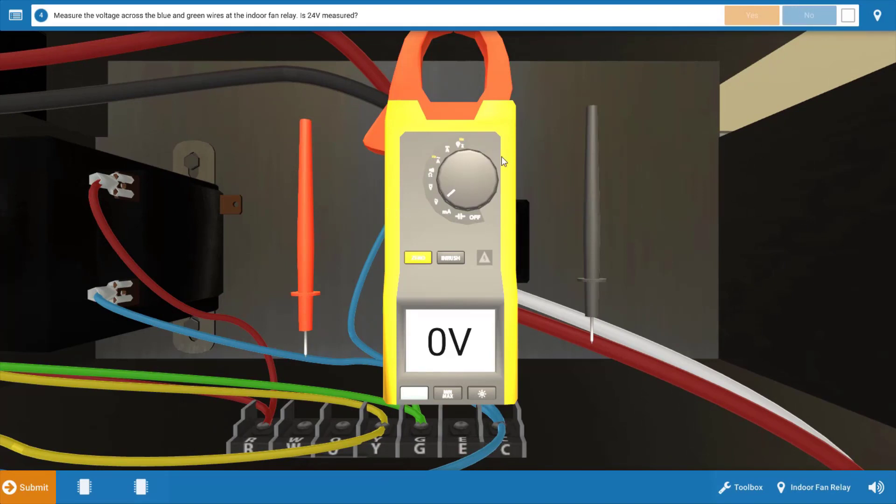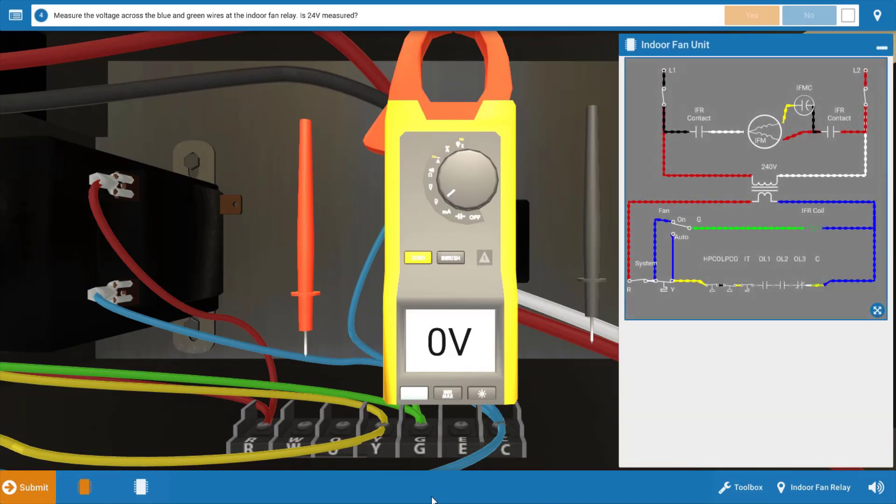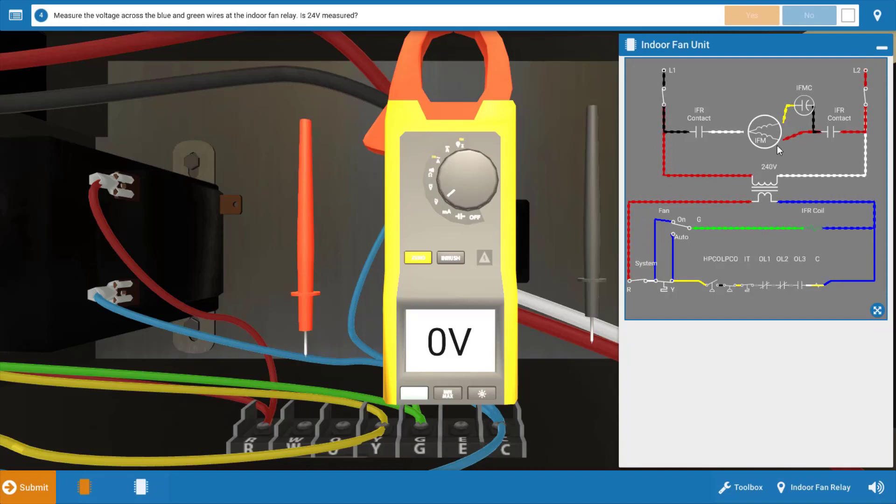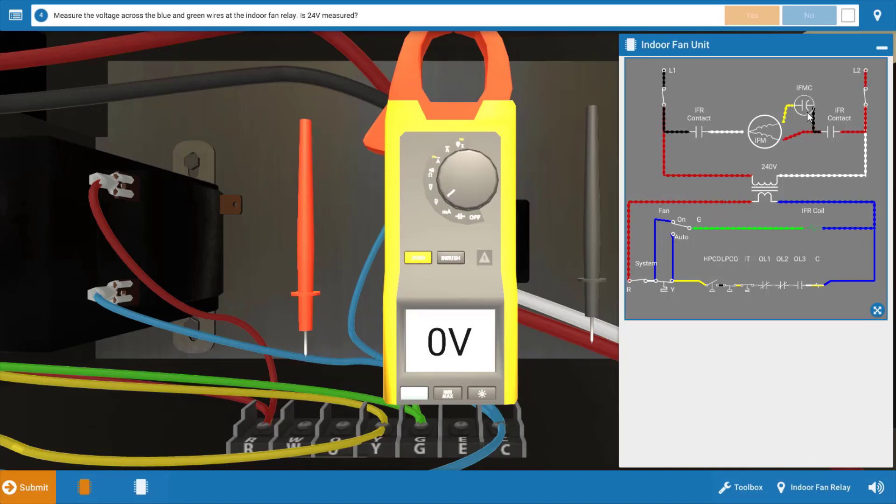Before we make any voltage checks, we're going to pull out the wiring diagram by clicking on the bottom left. Using the diagram, we're going to come up with a list of possible causes of this malfunction. The source of the problem is that the indoor fan motor is not running. So it's possible we have an open winding in the indoor fan motor. It's also a possibility that the indoor fan motor run capacitor located right here in series to the start line into the motor is faulty.